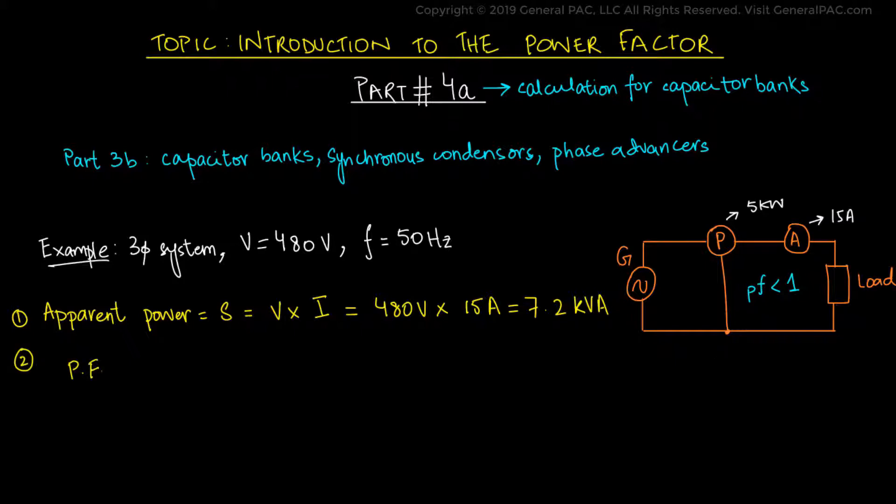The power factor equals the real power divided by the apparent power, which is 5 kW divided by 7.2 kVA, giving us 0.7. So the existing power factor is 0.7.